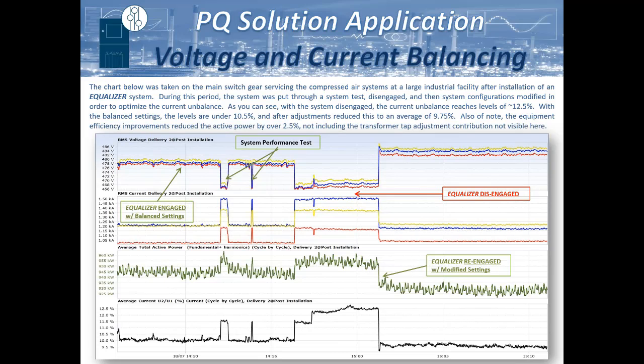This was a textile plant. This one system was installed on their compressed air network, which comprised about 12 or so large air compressors. Prior, when we were doing the baseline analysis, looking at what the profile looked like, we see this quite frequently in industrial applications: they were running at full load, and at full load we were seeing about 495 volts on a 480-volt network. So after installation, we were able to tap that transformer down by one level.